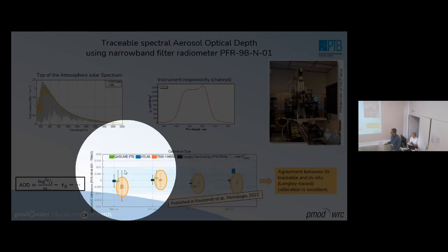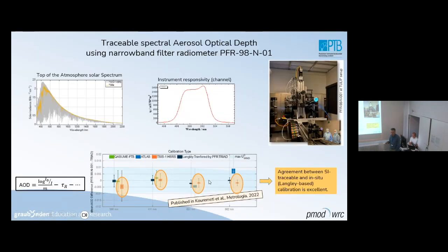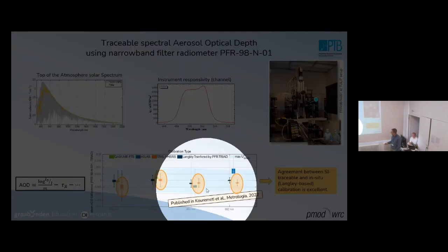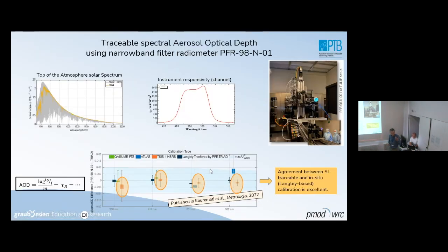And you can see here in light blue the boundaries of about 0.01 in optical depth, corresponding more or less to 1% uncertainty in the radiation measurements. And you can see that these highlighted dots here are all within less than 0.5%. So the procedure worked really well with our PFR instrument. And so we were quite hopeful that we could extend that work on additional instruments from other networks, like from the CIMEL or from the Skynet.